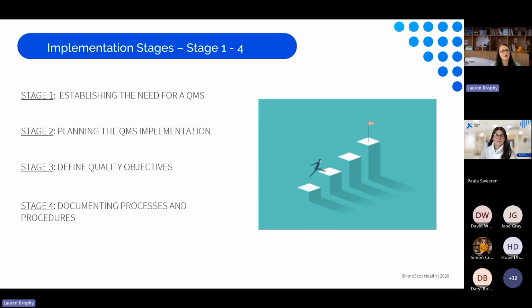So first of all, your stage 1, you need to establish the need for a quality management system. So before embarking on the implementation journey, it's crucial to assess your organization's current quality management practices and identify the need for a quality management system. Recommended to conduct a gap analysis against the standards listed in ISO 13485 and determine which areas of your device do not meet the requirements and define the scope of your work. So you would go through the ISO 13485 standard, you would determine the areas where your device meet those requirements, and obviously do a gap analysis where they don't, and you know which areas to strengthen on. Determining which parts of the standards are applicable, of course.